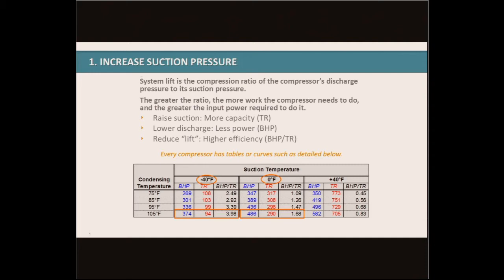When we're reducing the lift, we're getting a higher efficiency — lower brake horsepower per ton. This chart below is a standard chart we can get from any compressor manufacturer, and it shows the ratings of brake horsepower and tons for one compressor at a couple different set points.